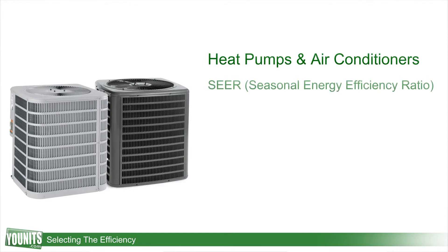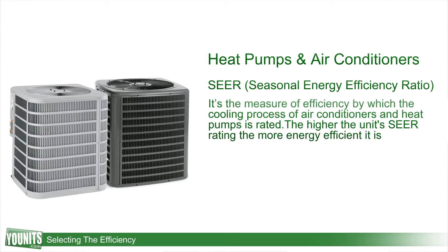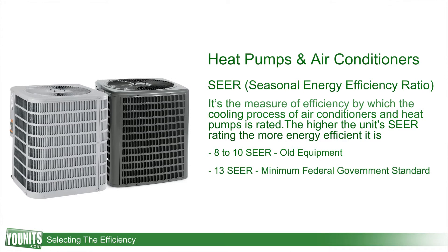The last acronym I want to talk about is your SEER rating, which is Seasonal Energy Efficiency Ratio. That's relative to cooling — either from your air conditioning compressor or also from your heat pump. Older units were down in the 8 to 10 range. The new minimum government standard for a SEER rating for all new equipment is 13, and they go all the way up to 18 as a maximum SEER rating right now. That's going to give you an evaluation of how efficient your cooling equipment is going to be and how your dollars are going to be best spent.